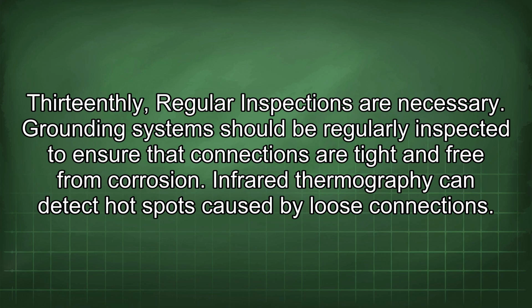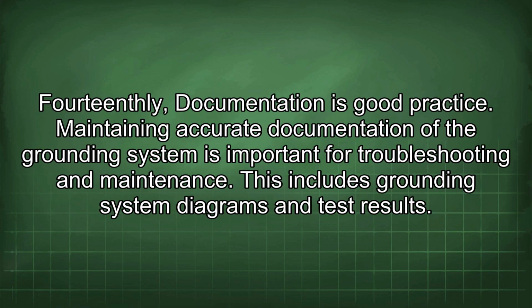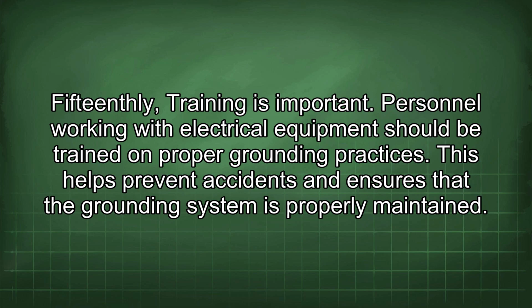Infrared thermography can detect hot spots caused by loose connections. Fourteenthly, documentation is good practice. Maintaining accurate documentation of the grounding system is important for troubleshooting and maintenance. This includes grounding system diagrams and test results. Fifteenthly, training is important. Personnel working with electrical equipment should be trained on proper grounding practices. This helps prevent accidents and ensures that the grounding system is properly maintained.